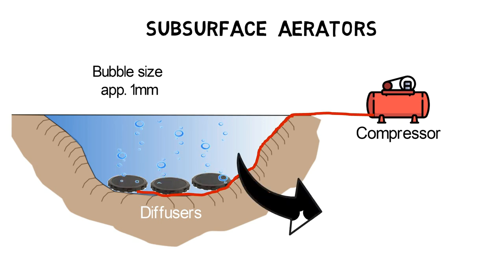The membrane perforation of fine bubble strip diffusers is microscopically small and released bubbles have a size of about one millimeter. Compared to surface aerators, fine bubble diffusers have in general a better oxygen transfer rate. Fine bubbles have a large surface area and they rise very slowly, which means that their contact time with water is much longer compared to propelled water droplets.